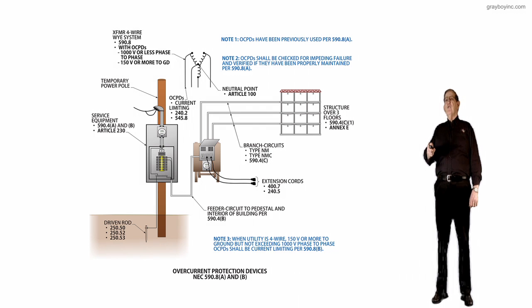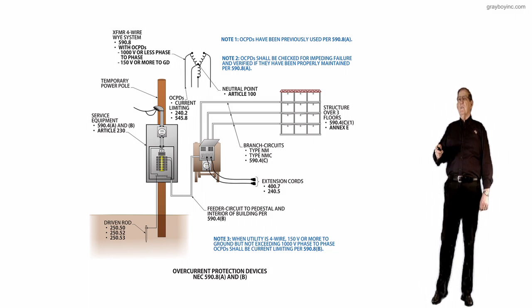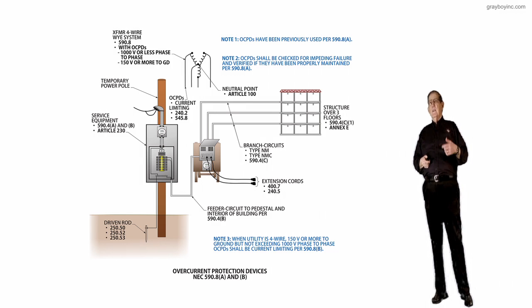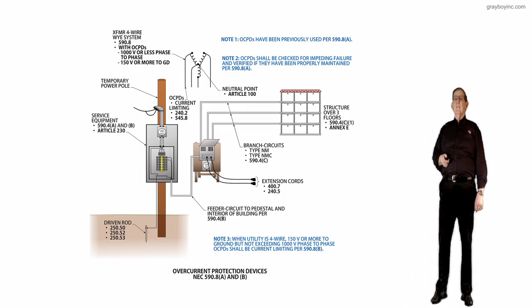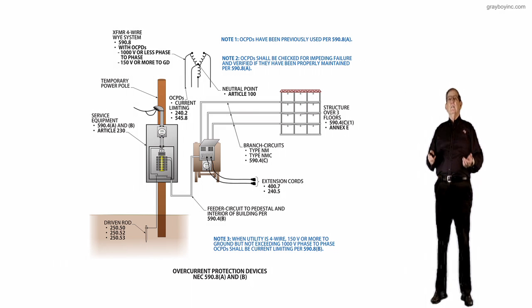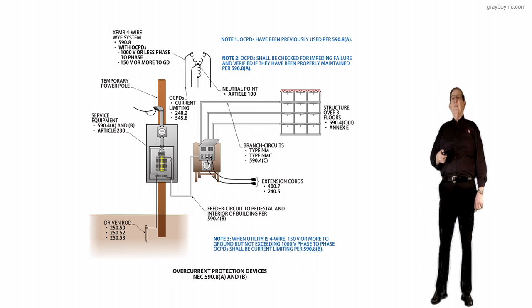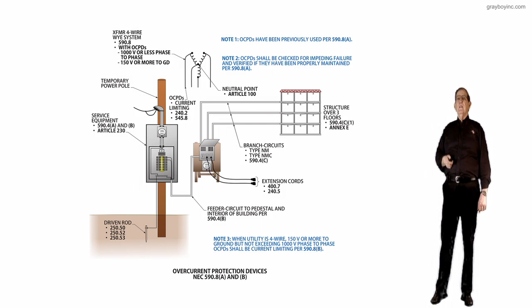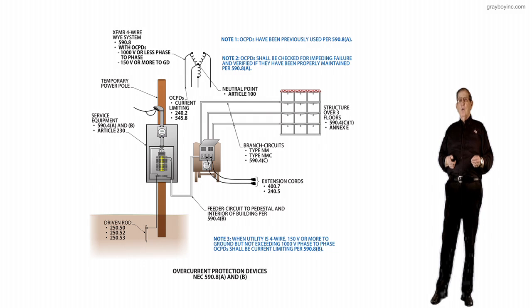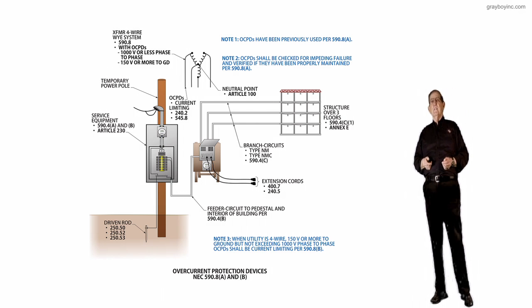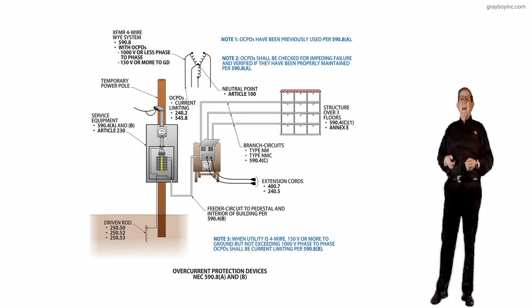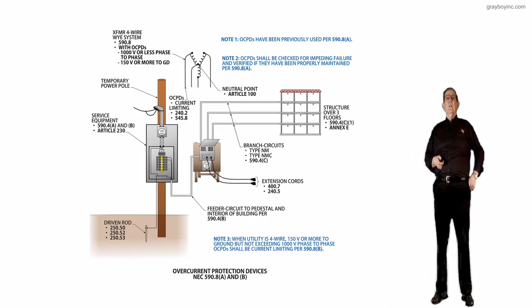590.4(C). And notice your structures, the floors could be wired with these wiring methods over 3 floors, as long as you wire them in accordance with 590.4(C)(1) and your Annex E in the NEC in the back of the code. So we kind of pick up these rules, and then of course your overcurrent devices fed from that 4-wire system transformer you see there right below it. You see they must be current limiting in accordance with the definition of current limiting in 240.2 and then section 445.8(B), and you would pick up 590.8(A) and (B), and you would have your rules for that. So those sections are important to me.